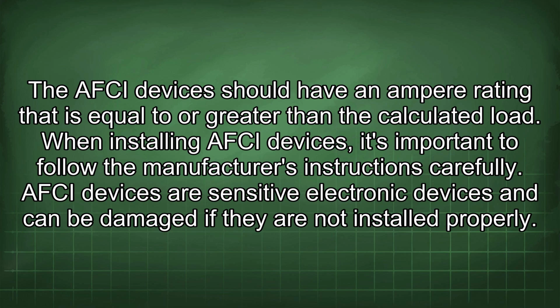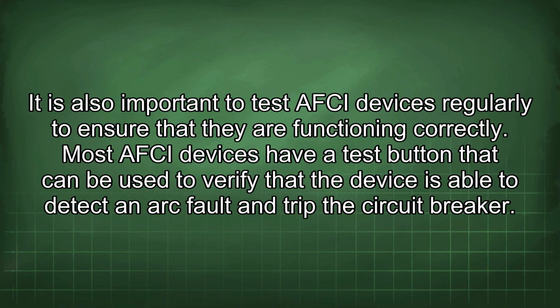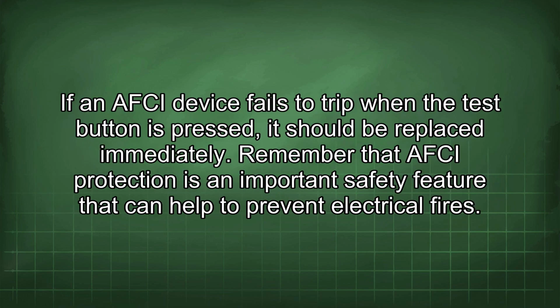When installing AFCI devices, it's important to follow the manufacturer's instructions carefully. AFCI devices are sensitive electronic devices and can be damaged if they are not installed properly. It is also important to test AFCI devices regularly to ensure that they are functioning correctly. Most AFCI devices have a test button that can be used to verify that the device is able to detect an arc fault and trip the circuit breaker. If an AFCI device fails to trip when the test button is pressed, it should be replaced immediately.